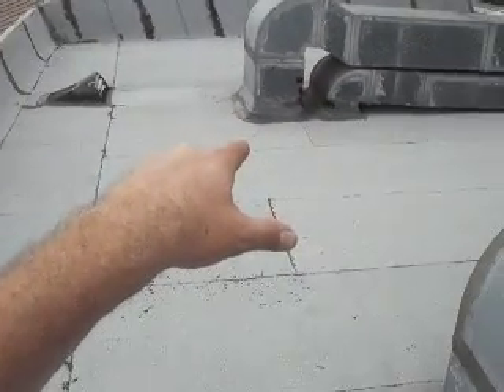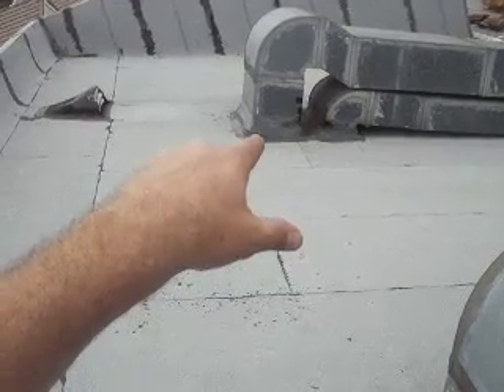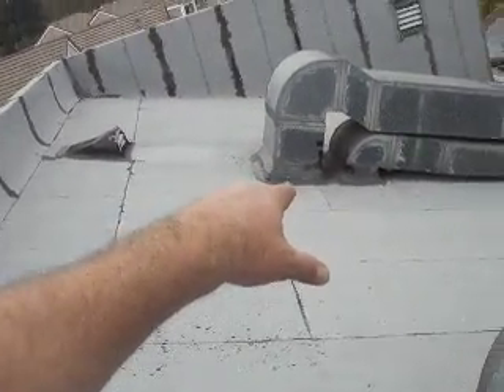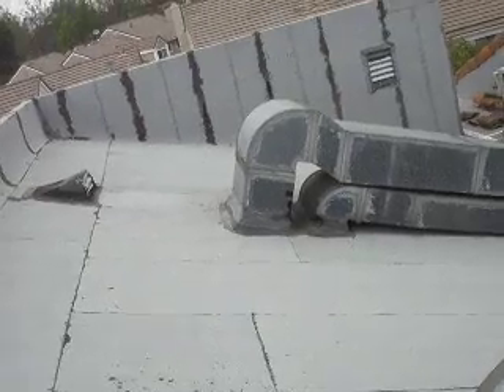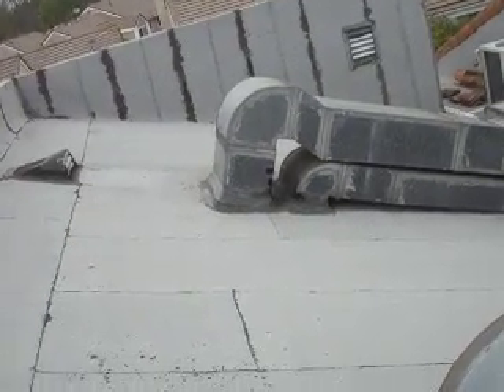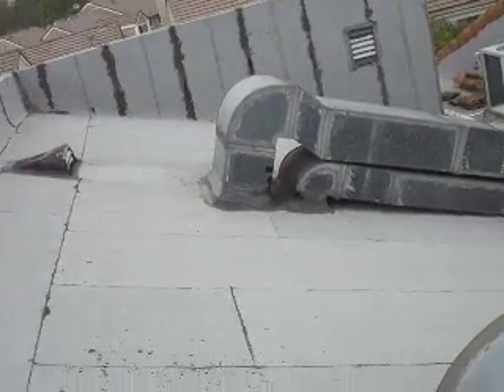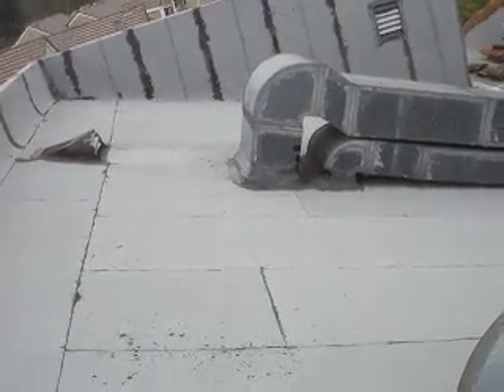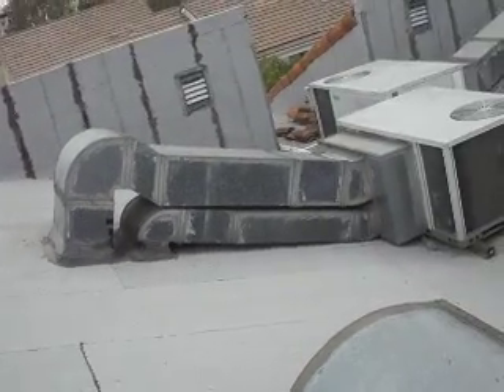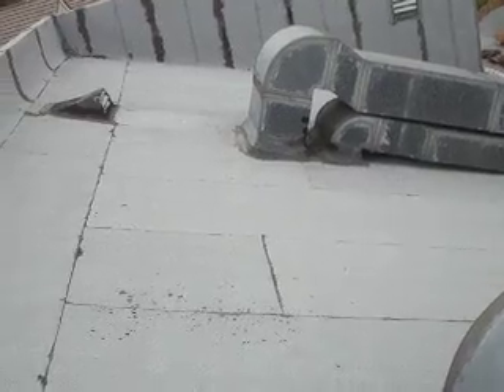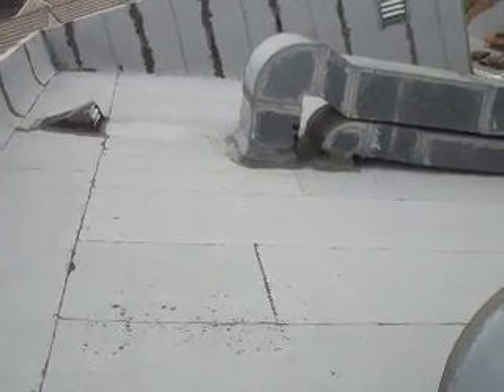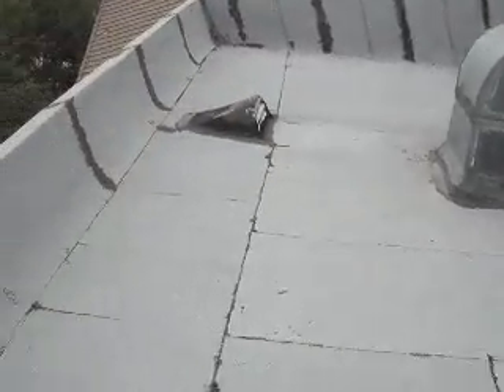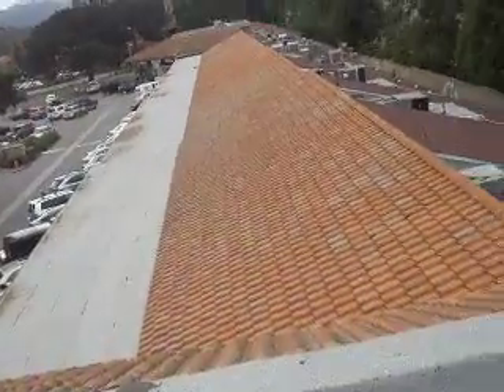Okay, and with the insulation up inside of this ductwork, the inside diameter is quite a bit smaller, right up around this choke point on this throat. That's the supply air on the bottom. And so what happens is I really can't put a full refrigerant charge in here because there's so much back pressure on the air that if I accepted a full charge in the unit, it actually runs the coil extra cold, then it starts icing up. And of course, when it starts icing up, the ice expands, and it expands the coil tubing in the coils, and then it stretches and it causes minute refrigerant leaks, which has been a problem with a lot of this equipment up here.